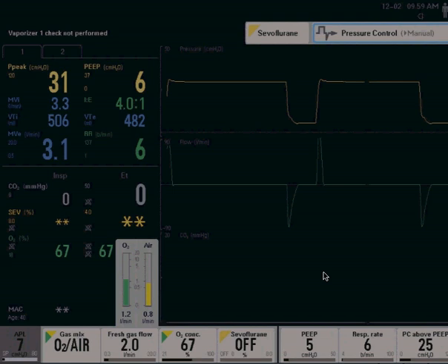So this is trying to mimic airway pressure release ventilation with an anesthesia machine. The Flow-i also has an added benefit, which is an active exhalation valve. I'm going to demonstrate that in the next video, where the patient can always breathe on top. That's the true heart of airway pressure release ventilation. The patient can spontaneously breathe anywhere in the inspiratory or expiratory phase, so you have unhindered spontaneous breathing. So I'm going to go ahead and show that.